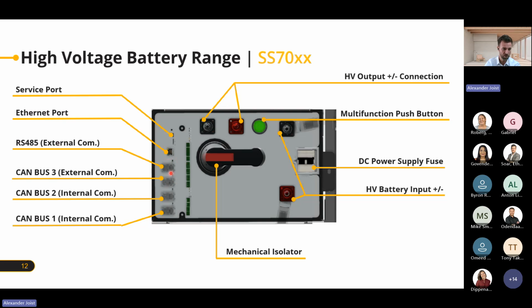One communication port, the top one here, has two different connections - either a CAN bus for external communication or RS485, depending what we connect to. This is the internal communication at the bottom, which is CAN bus 1 and CAN bus 2 for internal communication. On the right side at the top we have our high voltage connection, towards the inverter or the outside, positive and negative. And on the right side here it's positive and negative connecting to the high voltage batteries underneath the BMU.